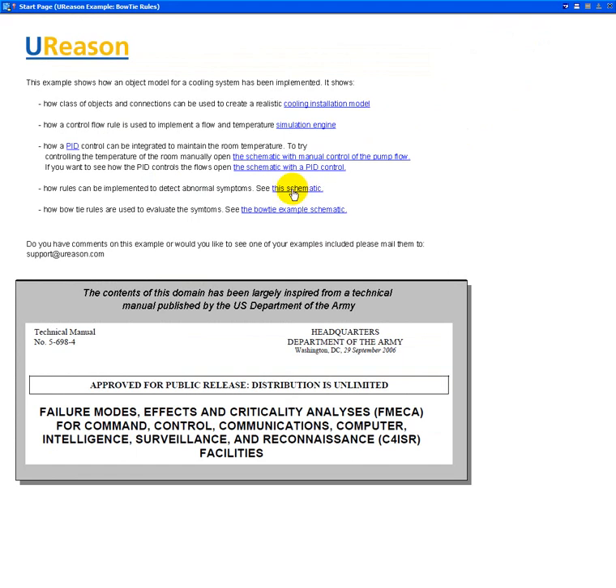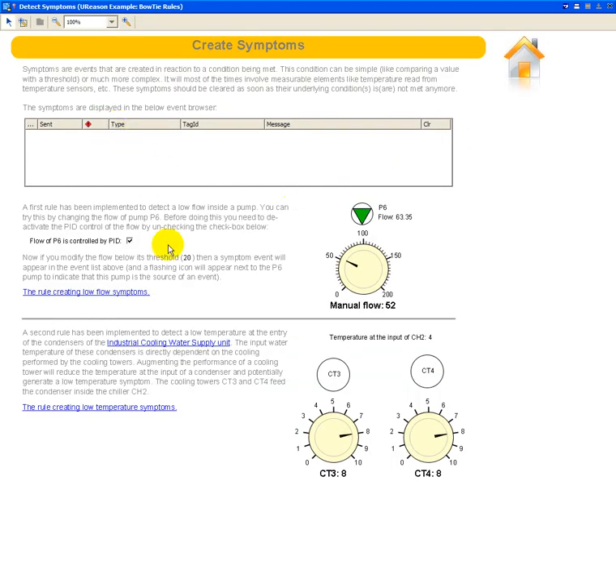The fourth part of this demonstration is showing how rules can be implemented to detect abnormal symptoms. And this is done on this page here, where again we are playing with the P6 pump, and what I'll do here, I'll also take control manually of the flow of that pump. It's actually now around 50, but if I for any reason decrease that flow below a certain threshold that is now set to 20, then a rule will react so if I go below, and generate an event to indicate that the flow of P6 is below its threshold, and a little icon appears here. If I control again this value and set it back to a value higher than 20, the event is cleared and disappears from my event browser here. The same would be valid for these cooling towers, but I will not demonstrate that right now here.